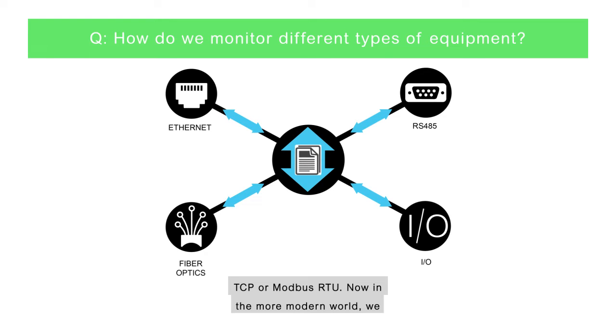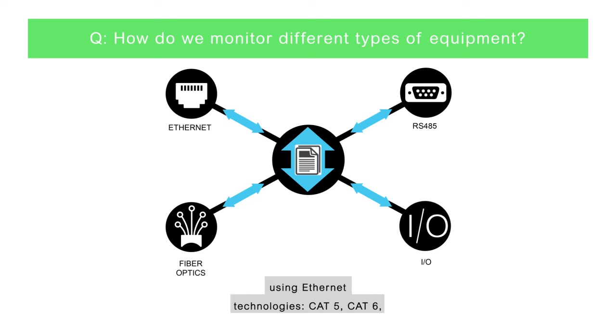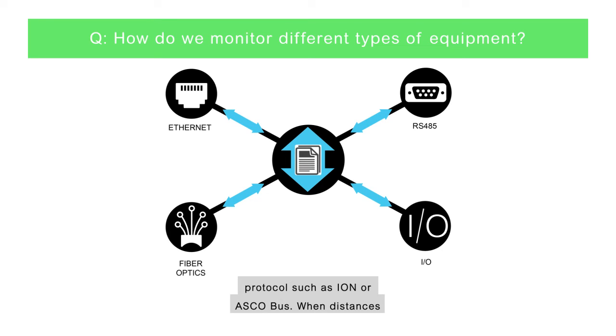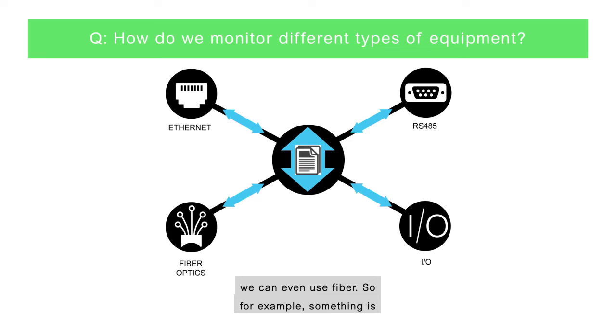Now in the more modern world, we do more data over other types of media, particularly using Ethernet technologies — CAT5, CAT6. We're really getting Modbus TCP or proprietary protocols such as Ion or ASCO bus. When distances, bandwidth, or noise immunity comes into play, we can even use Fiber.